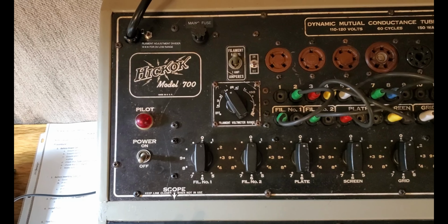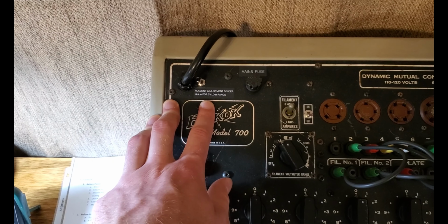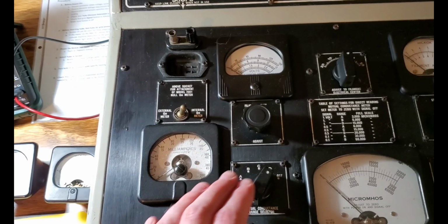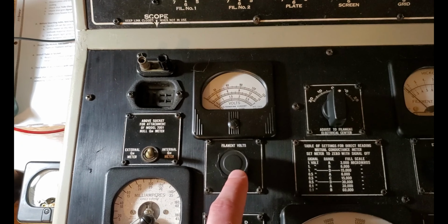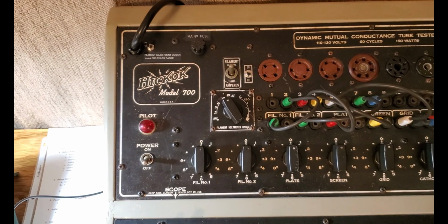And then the second one is the position of a high power resistor relative to this voltage adjustment, the filament voltage adjustment rheostat. So depending on this switch range, there would be a resistor either on the high side or the low side of that rheostat to change the adjustment range in order to get the full adjustment range of voltage depending on your tube current.